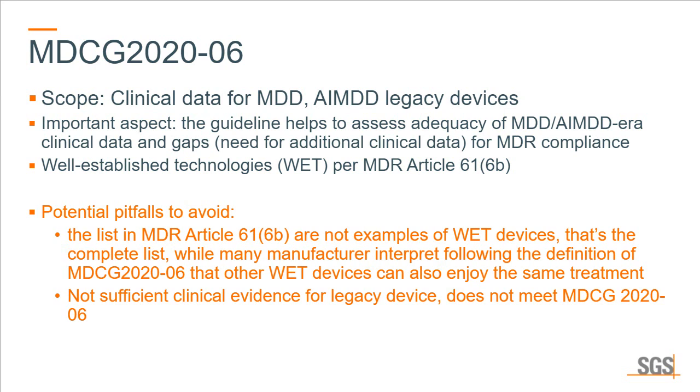So just because your device may also fulfill the definitions and the considerations of a well-established technology, it does not mean that you can automatically apply the exemptions that are listed in the MDR article. So just because your device is also a well-established technology, it doesn't mean that you will have some exemptions in the sampling or in the clinical evaluation section.